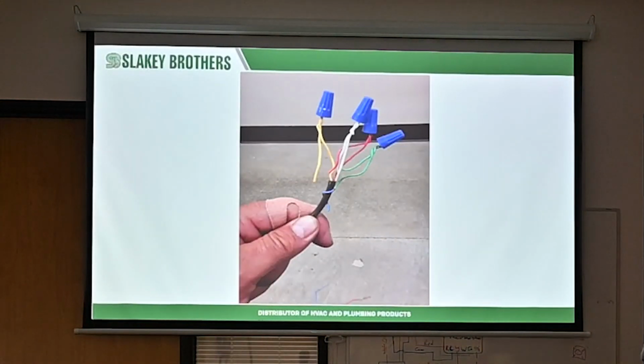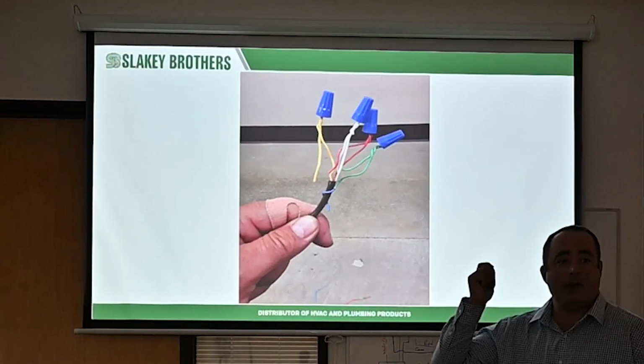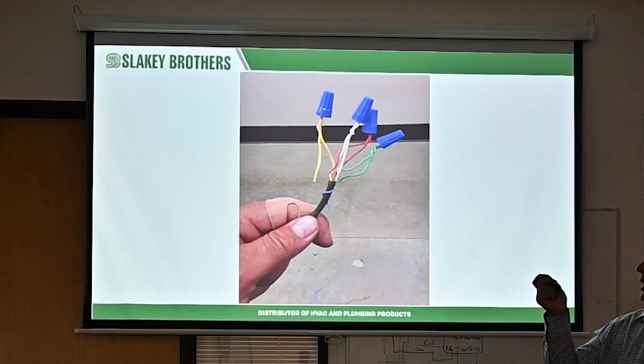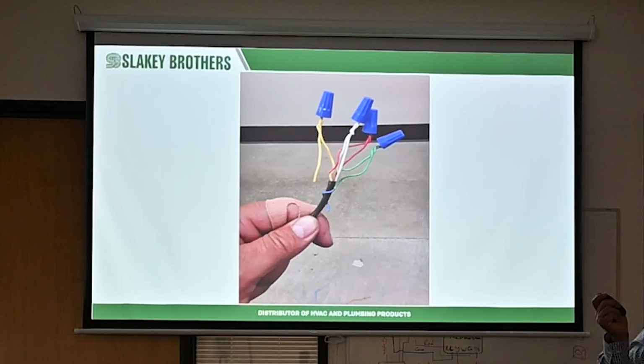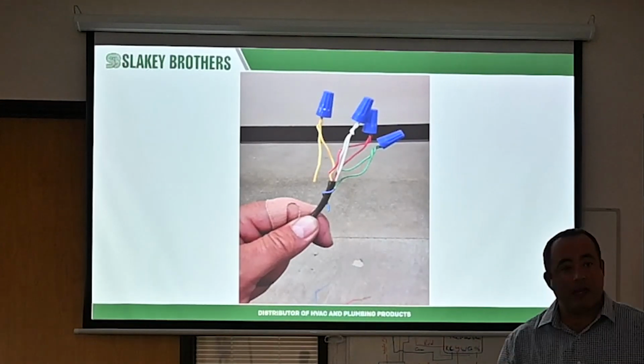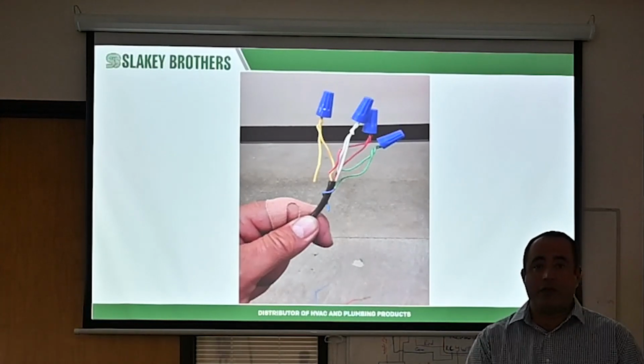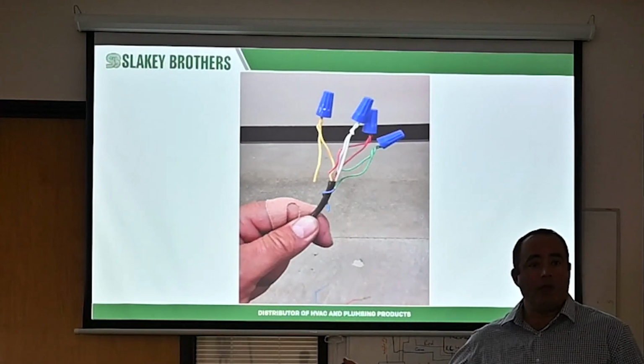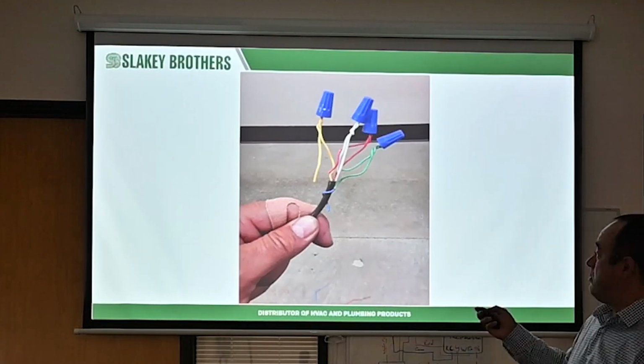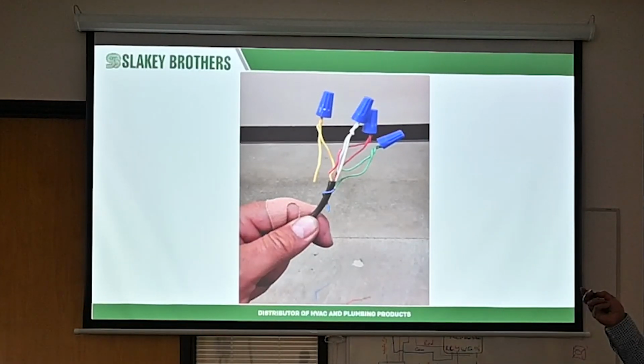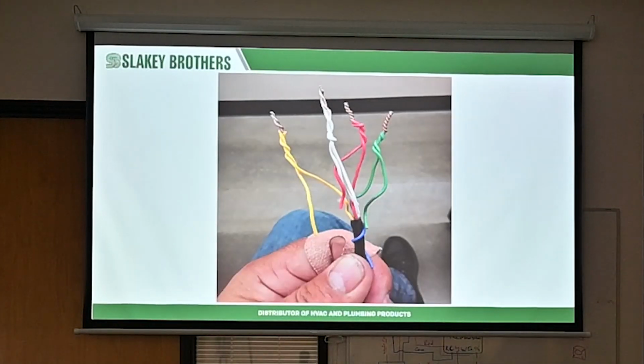This is old school. This is from our old display that we had from a long time ago. And I brought this out because this is a big no-no that they don't want you to do if you have to splice wire together. If you're doing a change out, a lot of times it's difficult to run a new line set, or it's difficult to run a whole new low voltage line to the outdoor unit. So if it's short and you have to extend a little bit, don't use wire nuts. Use butt connectors. Hell, you solder it and then shrink wrap it, whatever you have to do.